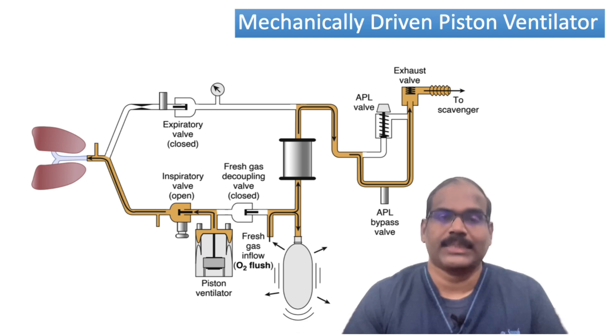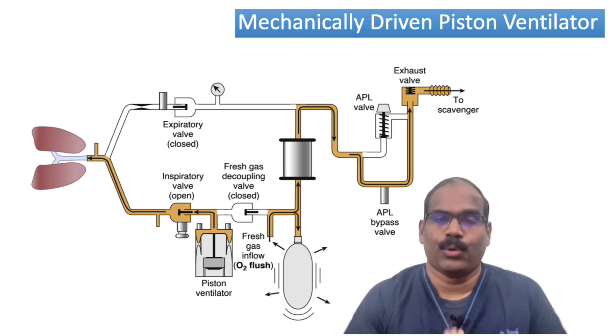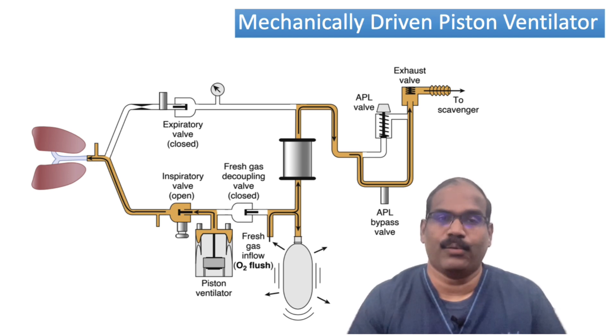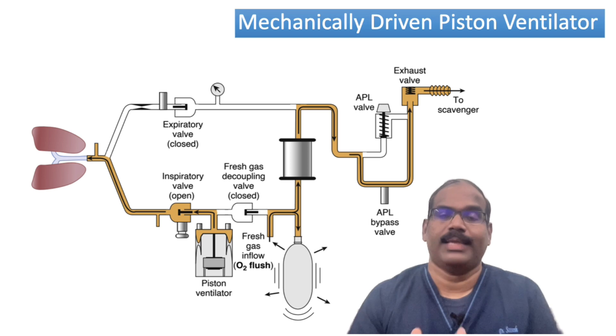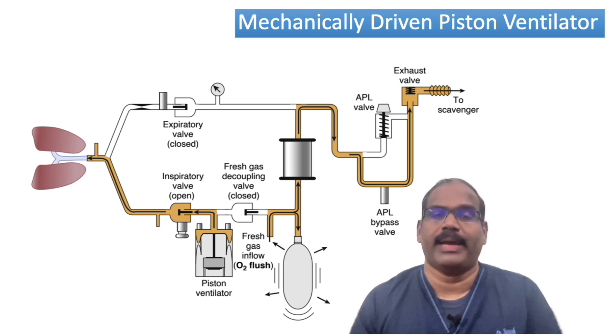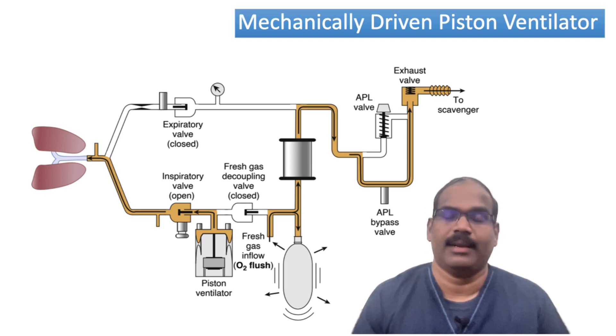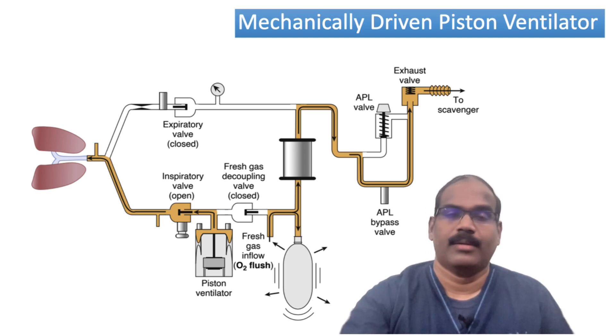Because of the fresh gas decoupling valve, when it is closed during the inspiratory phase, even if O2 flush is pressed, the pressure or excess gas gets buffered by the reservoir bag and is completely cut off from the inspiratory limb going to the airways.